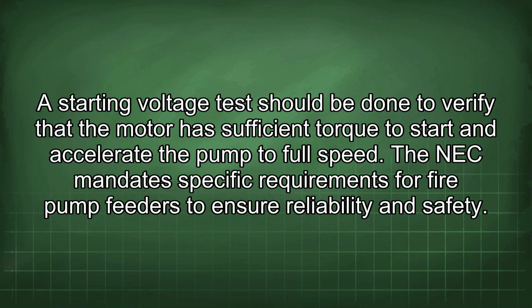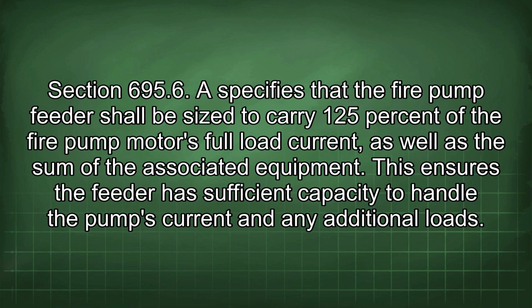The NEC mandates specific requirements for fire pump feeders to ensure reliability and safety. Section 695.6 specifies that the fire pump feeder shall be sized to carry 125% of the fire pump motor's full load current, as well as the sum of the associated equipment. This ensures the feeder has sufficient capacity to handle the pump's current and any additional loads.